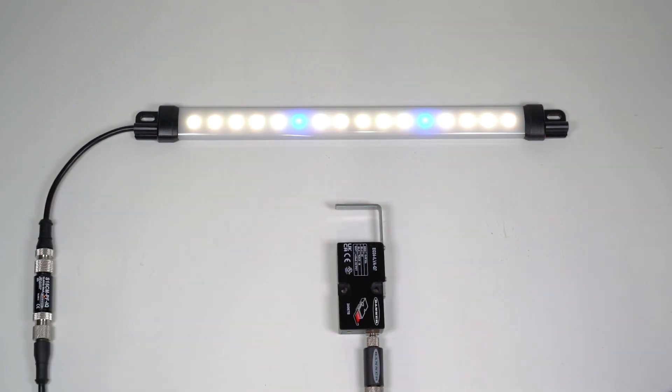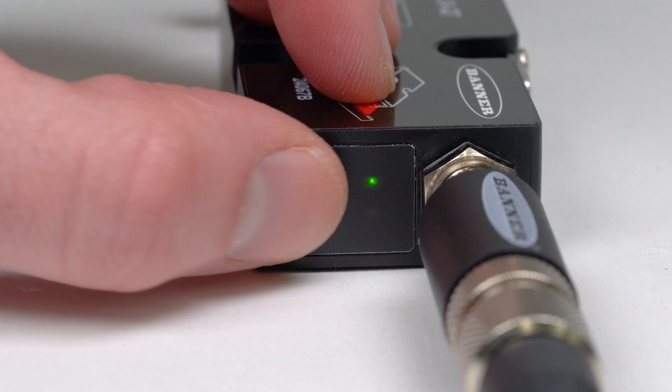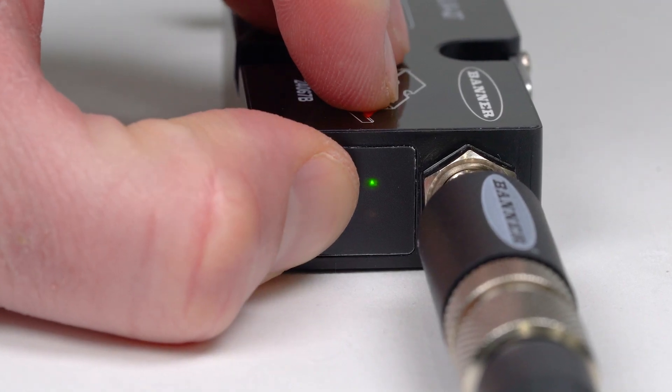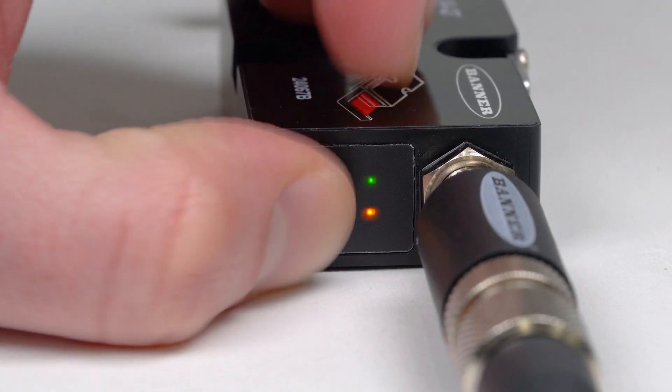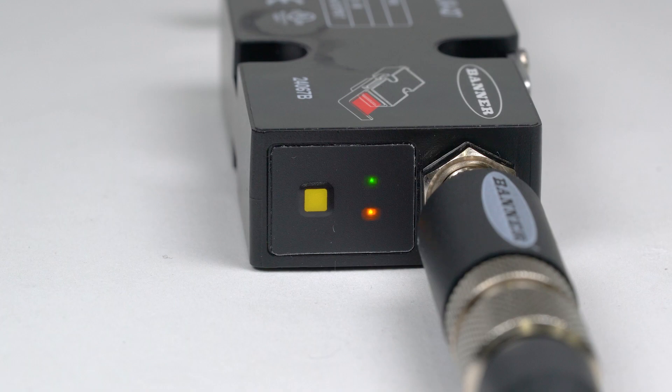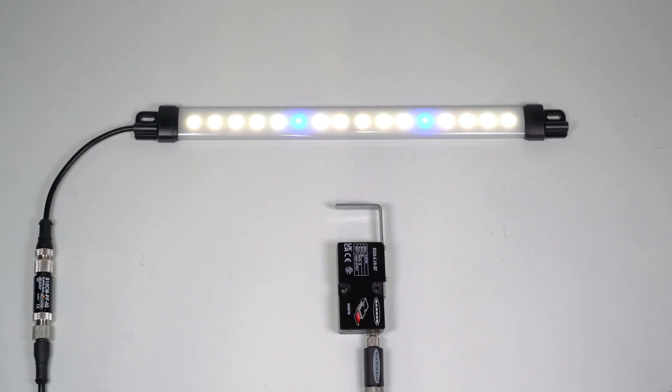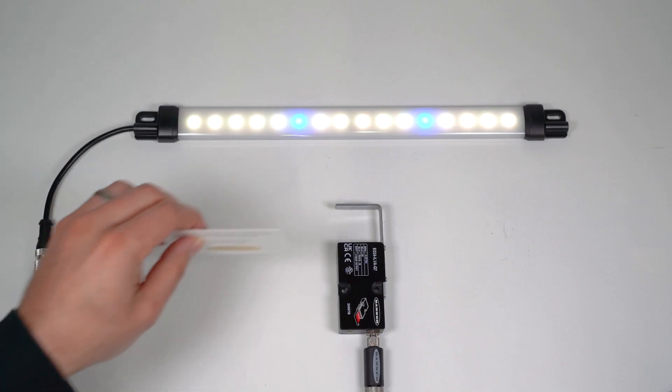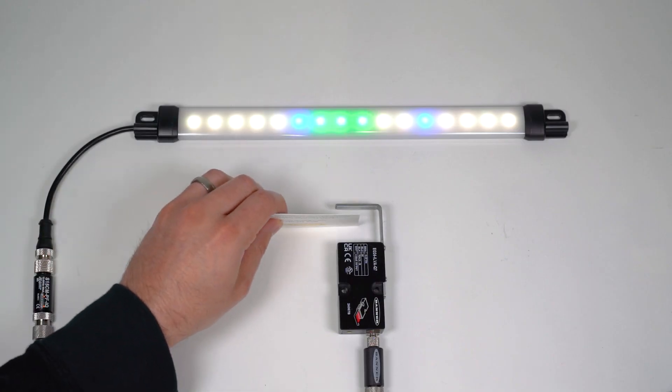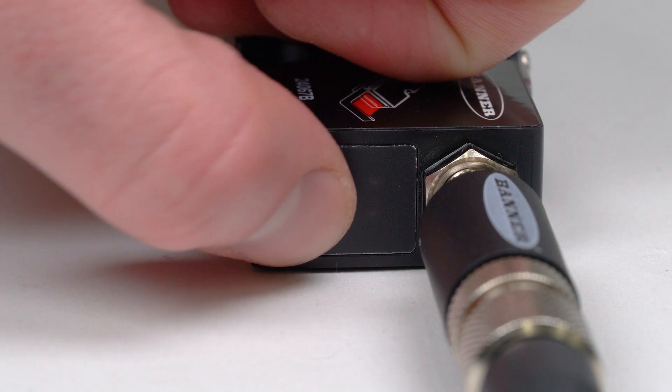To set the sensor to a smaller field of view for more precision, begin by pressing the button for two or more seconds until the LEDs flash in unison. Present a target in a position that will represent a 4 milliamp output signal and press the button one time.